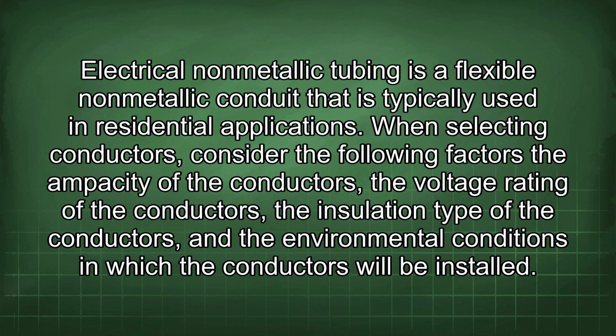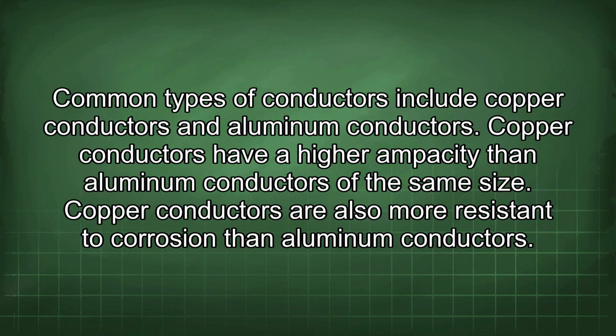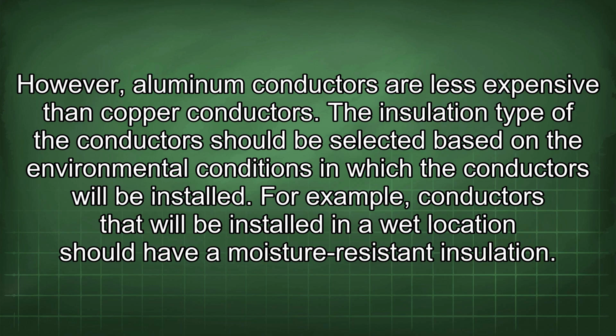When selecting conductors, consider the following factors: the ampacity of the conductors, the voltage rating of the conductors, the insulation type of the conductors, and the environmental conditions in which the conductors will be installed. Common types of conductors include copper conductors and aluminum conductors. Copper conductors have a higher ampacity than aluminum conductors of the same size. Copper conductors are also more resistant to corrosion than aluminum conductors. However, aluminum conductors are less expensive than copper conductors.